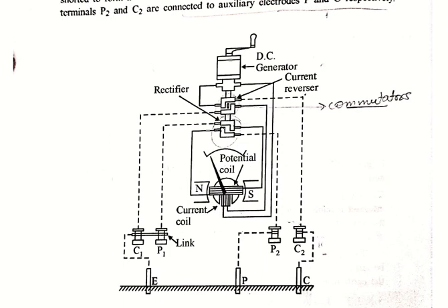Sending AC current through the soil has many advantages, and therefore this system is used. The use of AC passing through the coil eliminates unwanted effects due to the production of back EMF in the soil or electrolytic action. Also, the instrument is free from the effects of alternating and direct current present in the soil. So these are some advantages of using this earth tester. This is a basic kind of tester similar to the megger and having some features of PMMC.